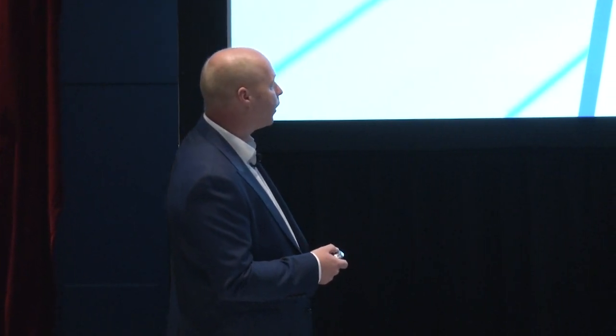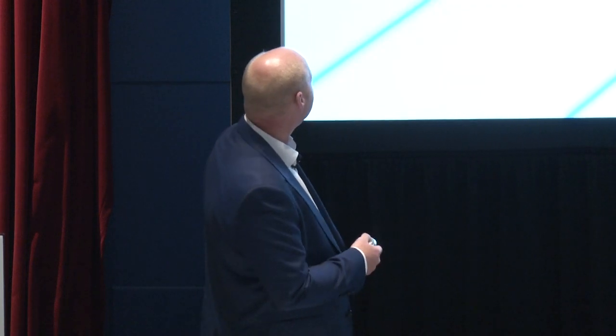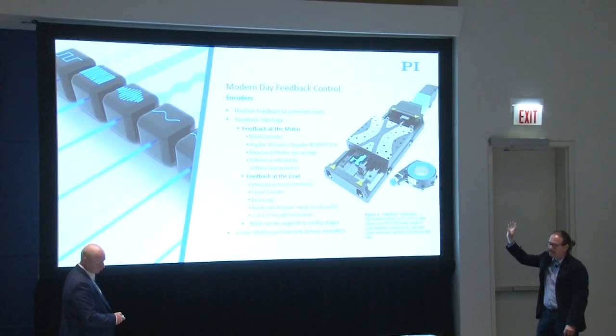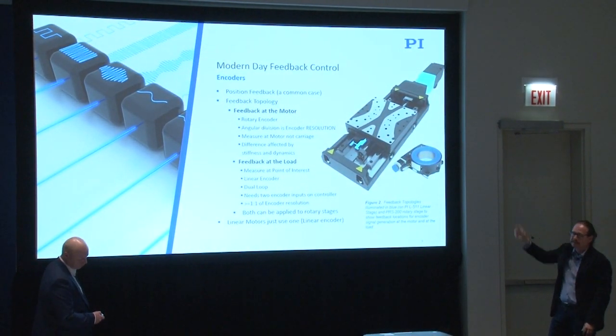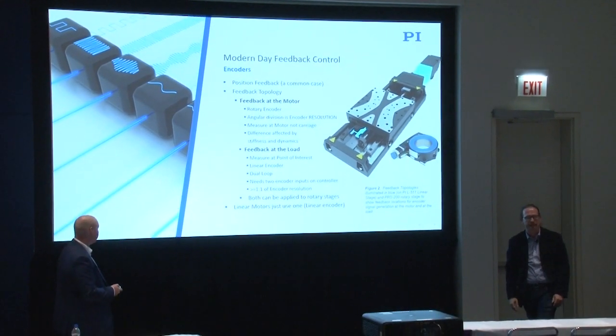Encoders have different protocols. In the upper left you have a square wave — what might mimic a quadrature A-B, or A quad B. For incremental and other protocols there's sine cosine. This goes into limitations and advantages, especially when you need to synchronize external devices to motion systems. Mounting the encoder at the load — on the stage with the linear encoder — tends to be the preferred option for precision applications.